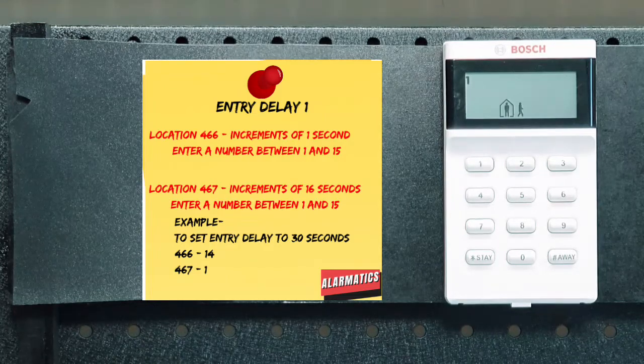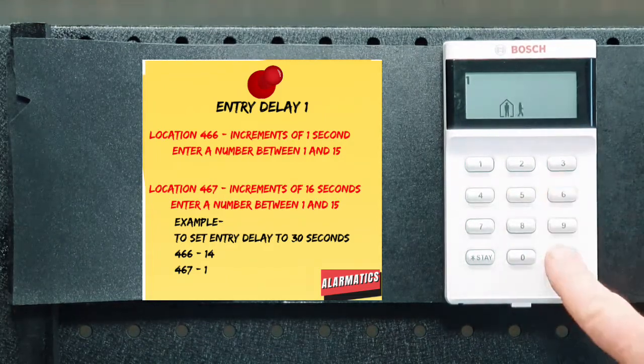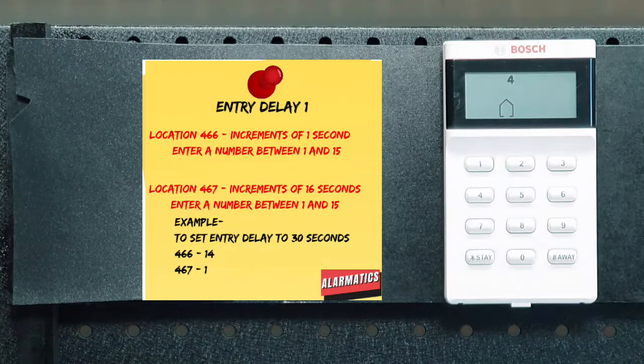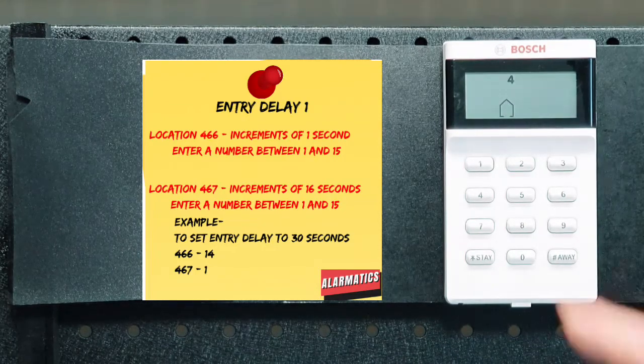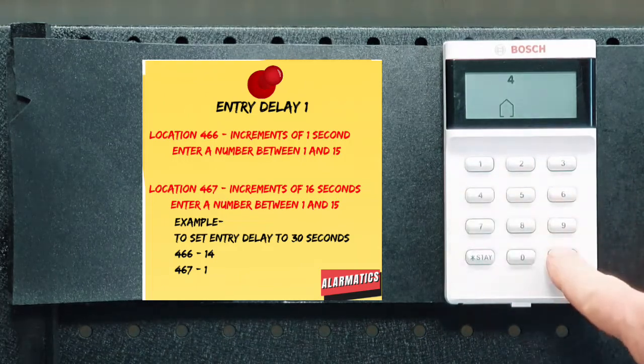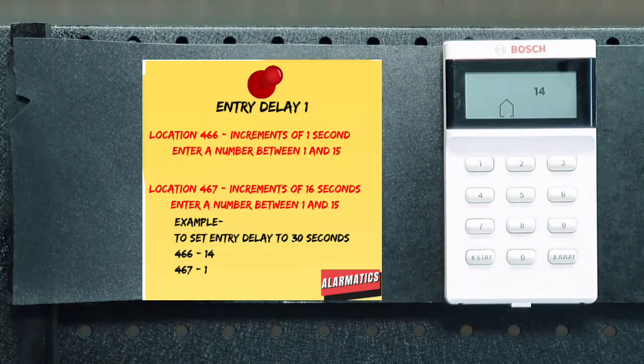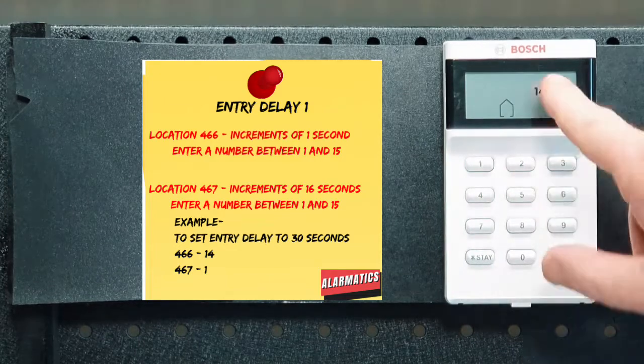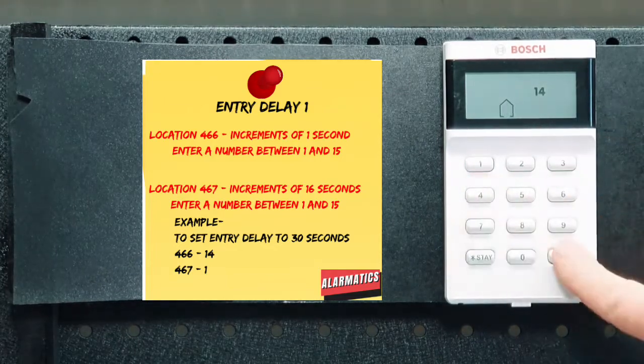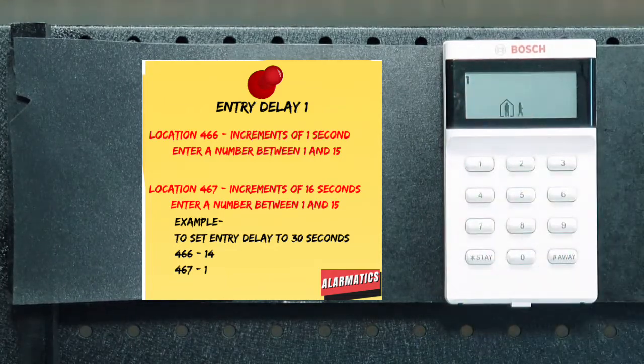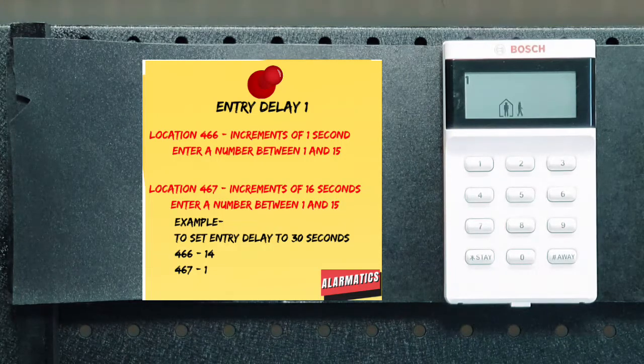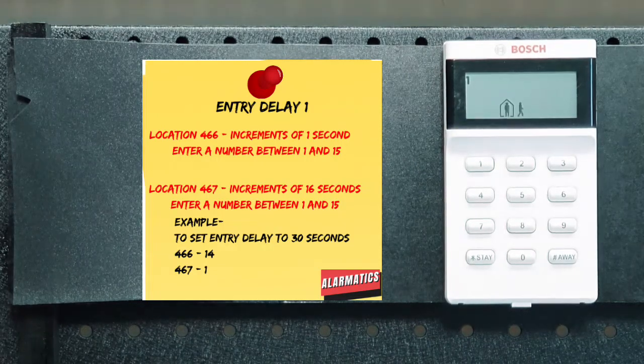Now I can go to 466, which is the individual seconds to build up the difference to get me up to 30 seconds. So in this case, it'll be 14, won't it? 14, and we save that. So in 466, we've got 14. In 467, we've got 1, so that's 1 block of 16 seconds at 467, plus the top up of 14 seconds at 466. 16 plus 14 gives us 30. Whew, guys, does that make sense? I'm making that sound harder than what it is.